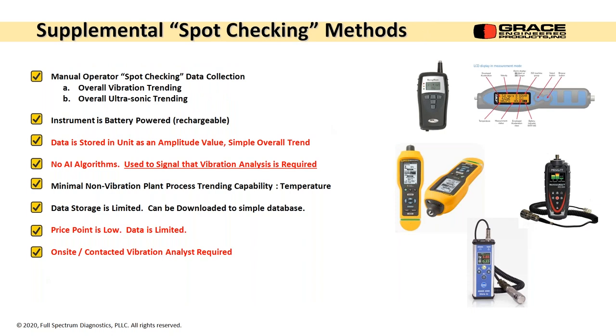Okay, there are supplemental spot checking methods. A lot of places will give the operators, like in power plants, an overall meter, and they'll go out. It's battery powered, storing just a value. There are no algorithms, and minimal vibration analysis training is required. Data storage is limited, but you can download it. Price is low, so it's good. You're making use of your operators, who would otherwise be walking around writing something on a clipboard. Instead, you're getting an actual measure. But it's only as good as the operators make it.